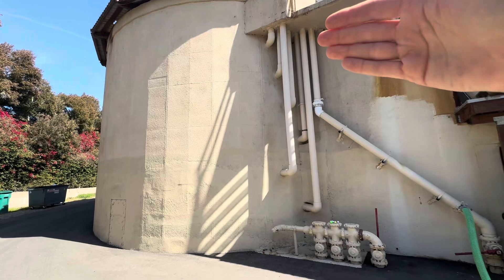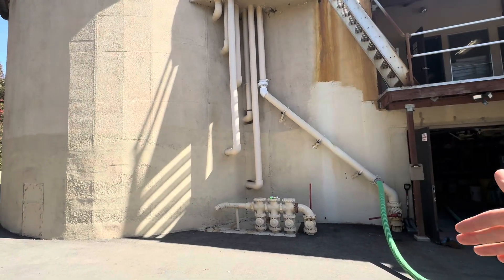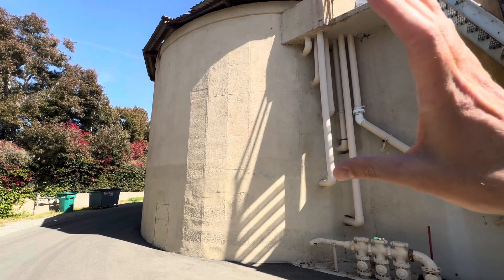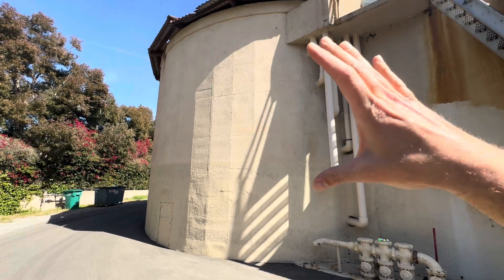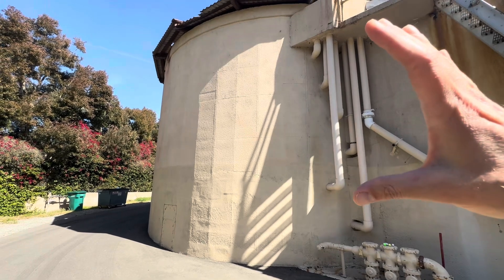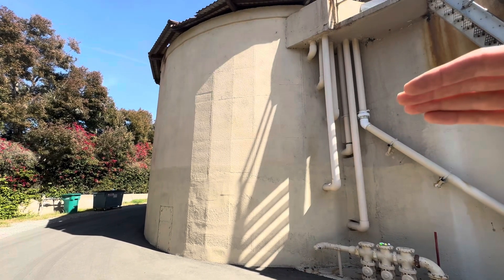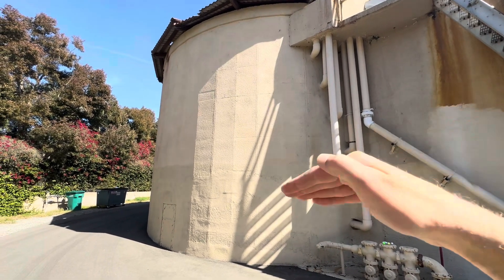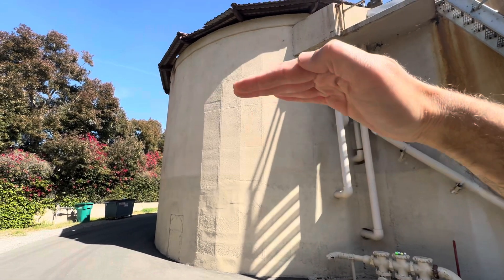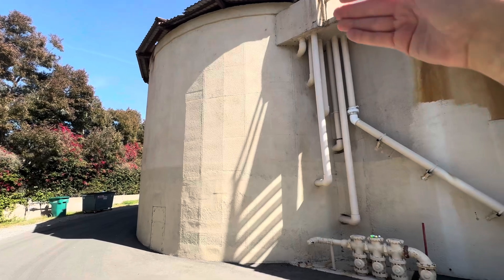The very next segment is going to be us repairing this line. And I'm going to explain that project in a second. But why we're going to repair the line is anaerobic digesters are typically full. Unless you're drawing sludge off, they're going to be full. And so whenever you pump thick, thickened sludge into it, there's water, there's a water layer in here and it's displaced and it has to go somewhere.